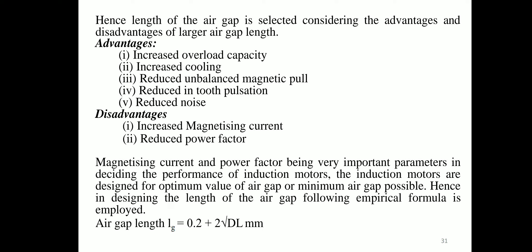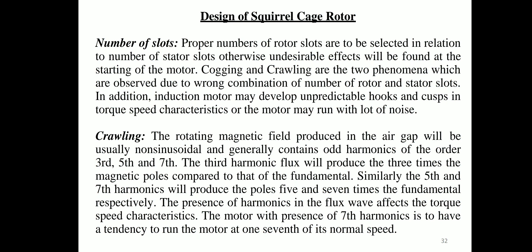For squirrel cage rotor design, proper number of rotor slots must be selected in relation to the number of stator slots, otherwise undesirable effects occur at starting. Cogging and crawling are two phenomena observed due to wrong combinations of rotor and stator slot numbers. Additionally, induction motors may develop unpredictable hooks and cusps in the torque-speed characteristic, or run with excessive noise.